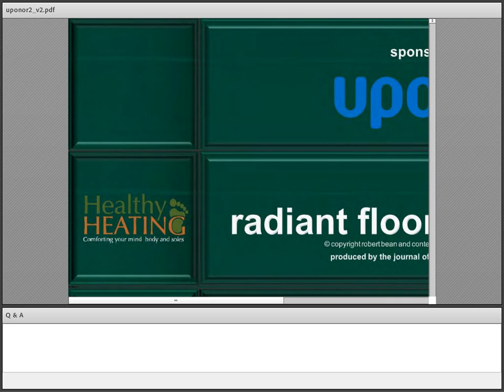And it also lends itself really well to renewable sources. One of the things we like about these systems is that the radiant component takes care of all of the sensible loads in a space, anything that has to do with energy transfer in the absence of moisture. And by doing that, we can then have an independent ventilation system, dedicated to bringing in outdoor air and conditioning that air for the purposes of providing healthy indoor air quality.